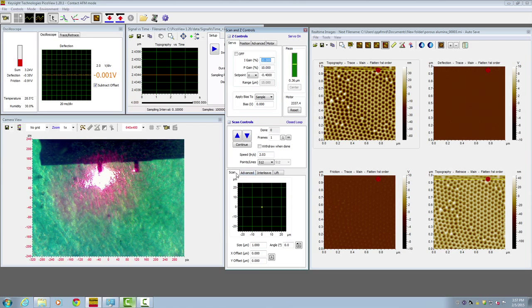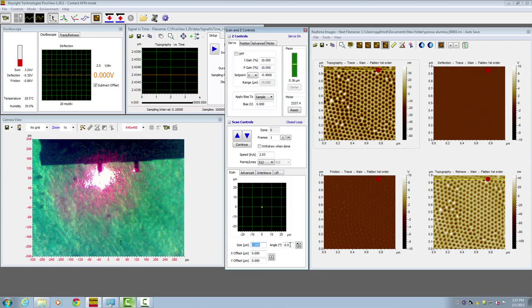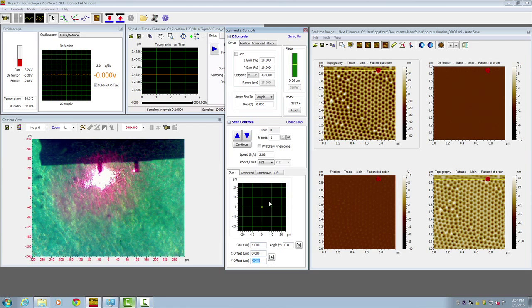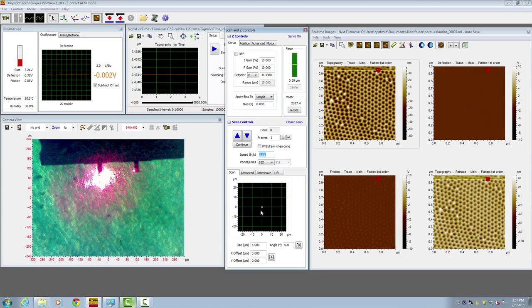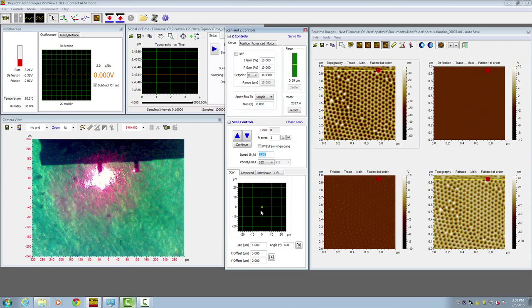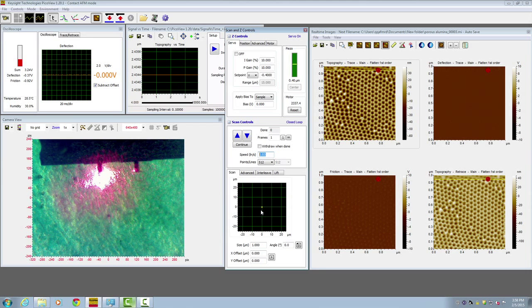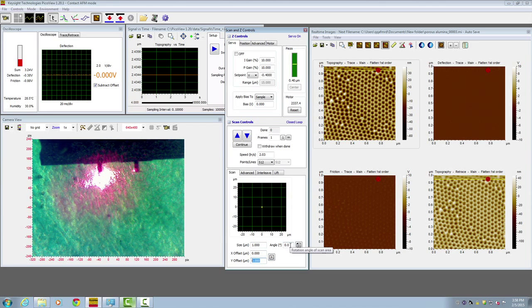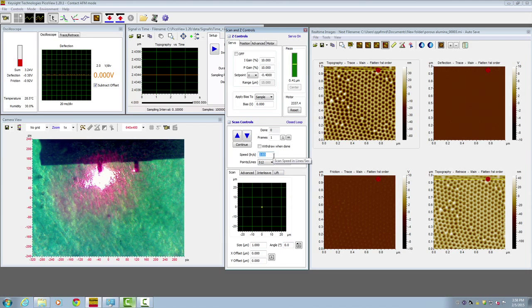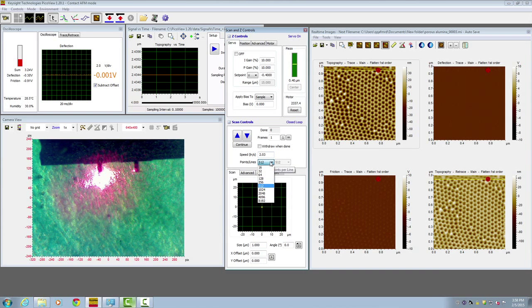Come to the scan window and type in the scan size, scan angle, XY offset, and scan speed. The rule of thumb for determining scan size is the feature you want to look at times 5 to 20. This sample has little rings that are about 100 nanometers, so we can image at 10 times 100 nanometers, which is 1 micron. We use a scan size of 1 micron, imaging in the center of the scan range, so XY offset is 0 and we'll image at 0 degrees of rotation. Speed is 2.03 lines per second and we use 512 by 512 pixels.